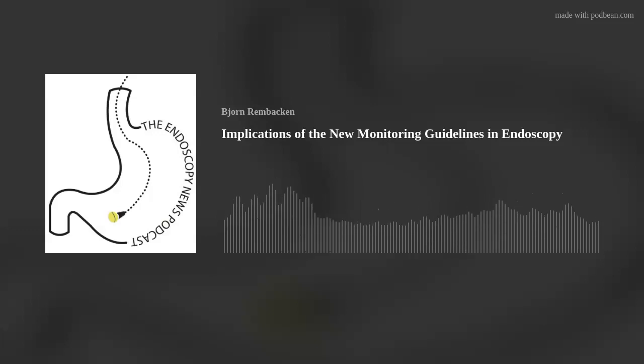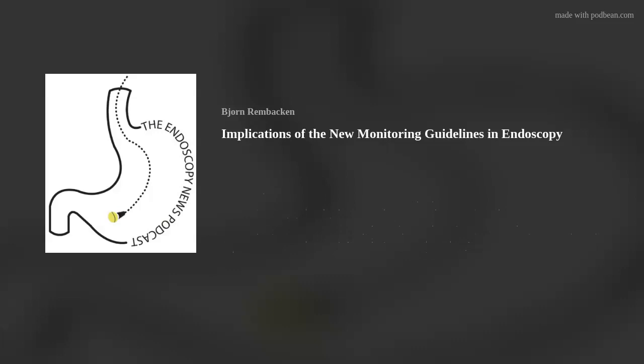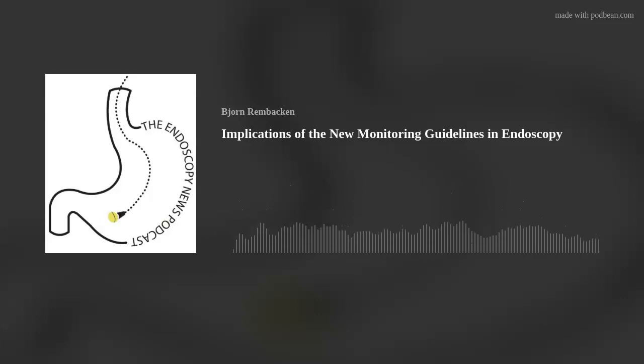And usually they create some sort of shenanigans where the little capnography probe is situated very close to the patient's mouth to still provide monitoring. But again, then the probe is not in a closed circuit. It's just next to the patient's mouth. And I guess you will lose some information in that change. Yeah, you need to bear in mind that the rate of fresh gas flow to the device, whether it's nasal cannulae or a face mask type device, will dilute the gases available to the sampling port. So when that happens at very high flow rates, potentially the peak expired CO2 will be diluted by the incoming oxygen. And that will appear relatively lower, but you will still see a waveform, most likely.